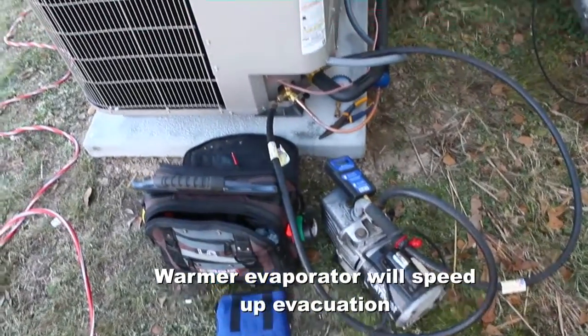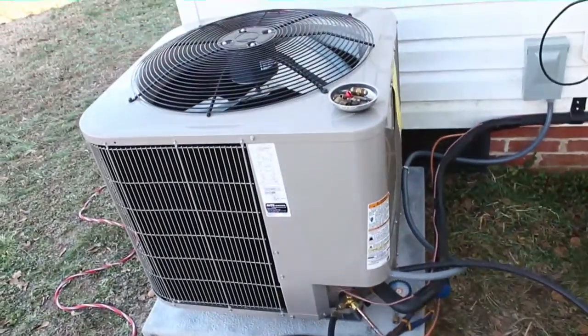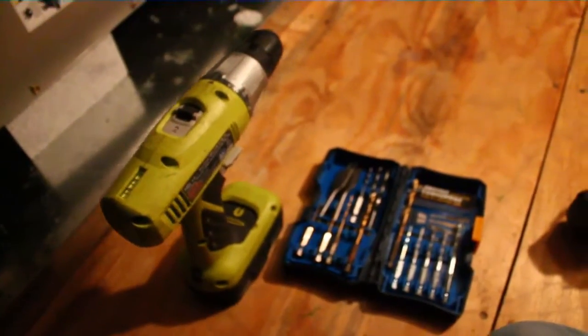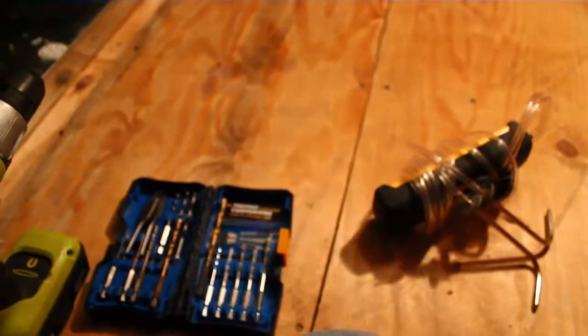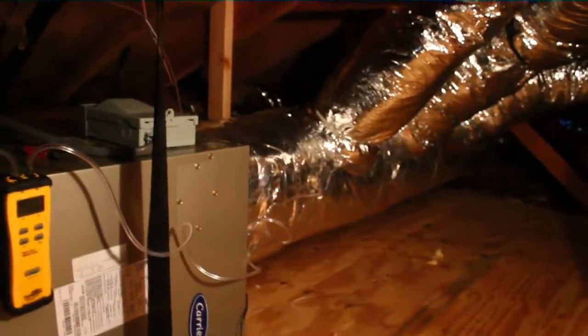But I'm going to go up in the attic and drill the holes for static pressure. We have a drill and our drill bit set here, and there's my static pressure, the old Fieldpiece, and the static pressure tubes. We're going to drill a hole here, and then one on the opposite end of the air handler, and see what we got going through there. Last time we had to drill a hole in the air handler because we had a media filter on the end of it, but this time, since the filter is at the grill, we can just drill it in the plenum. We have the Fieldpiece on here, one probe in the return box, one right around the corner there in the supply duct. You might see it, you might not. You're just gonna have to believe me.